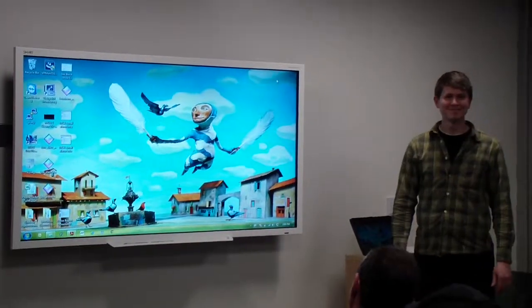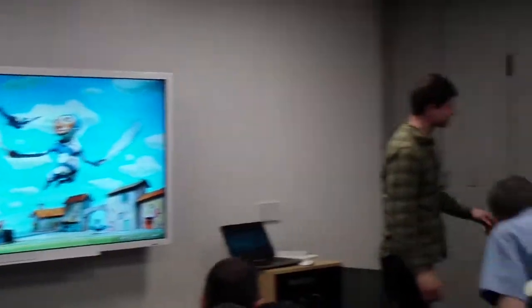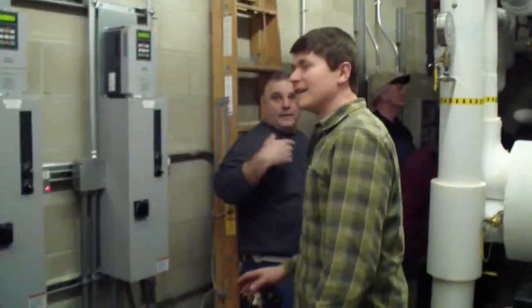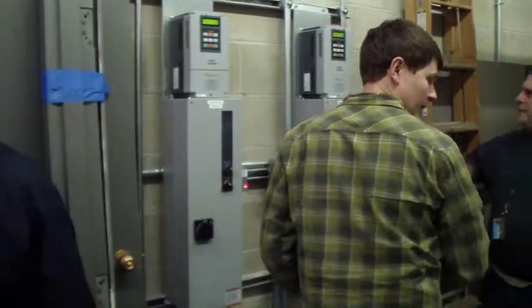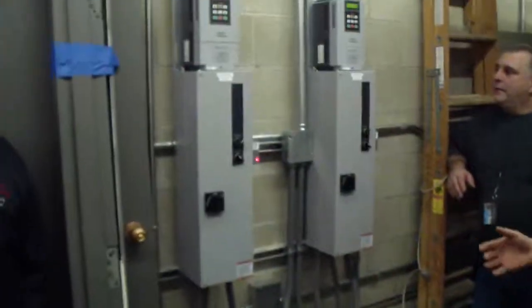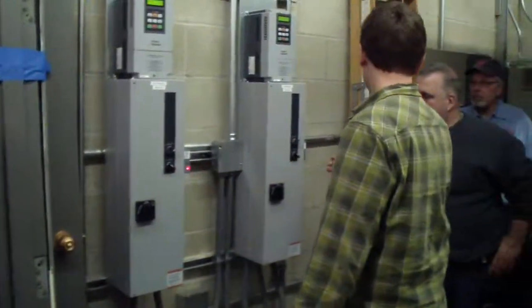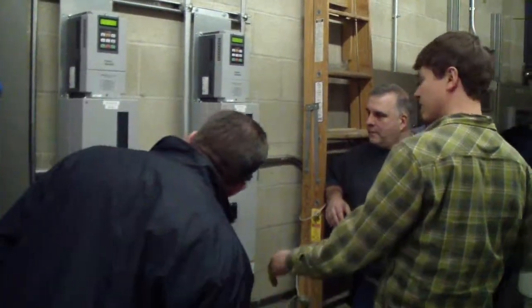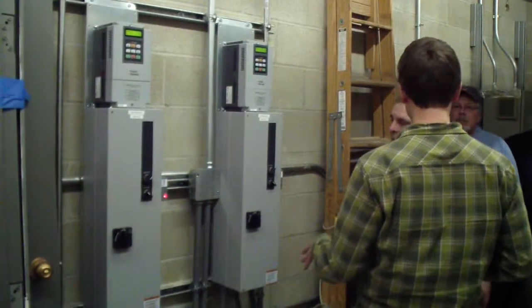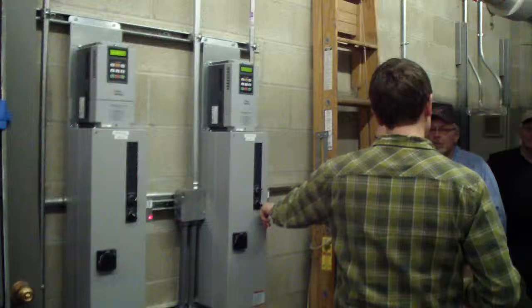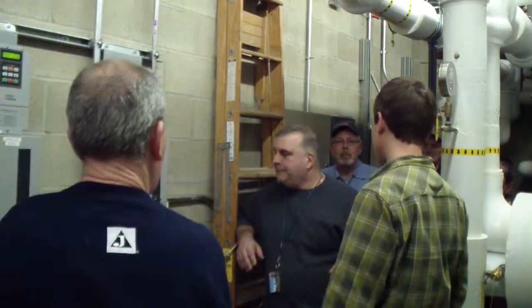You ready to go for a walk? So we can, oh, there we go. These are the drives for the pumps. You can see your two pumps in here. Oh, yeah, you've actually got a hand-off-auto for your start command on these. So if you're out here and you need to run one of them and it's not coming on, as opposed to throwing this, you can actually engage the relay that's here, and that will energize one of the drives. That'll give it the start.